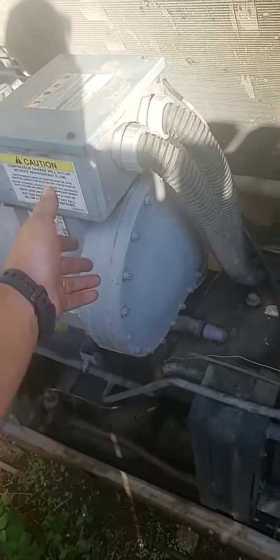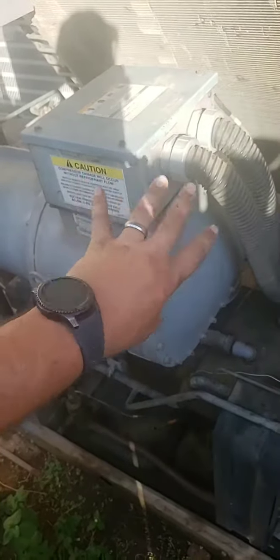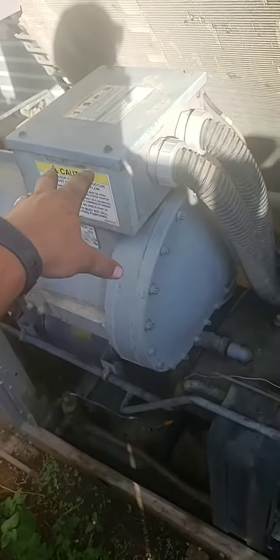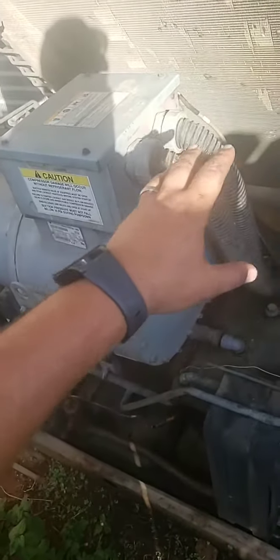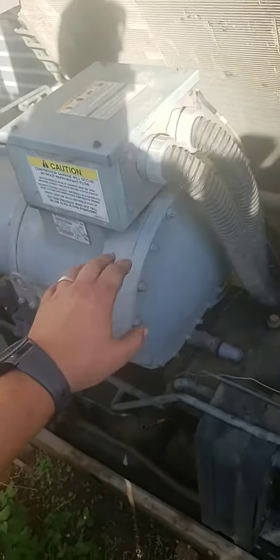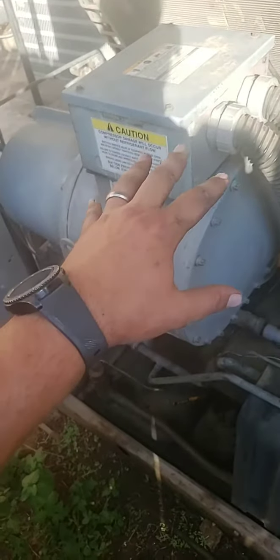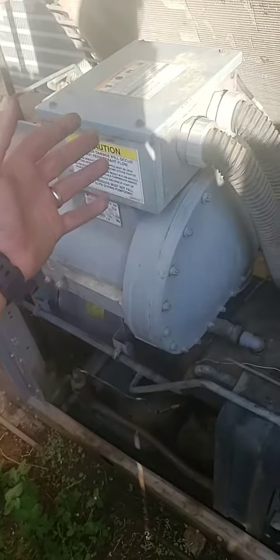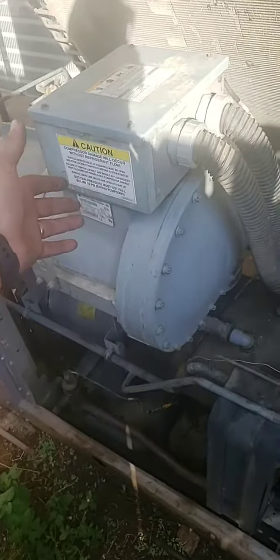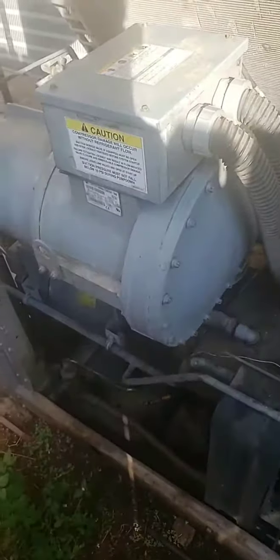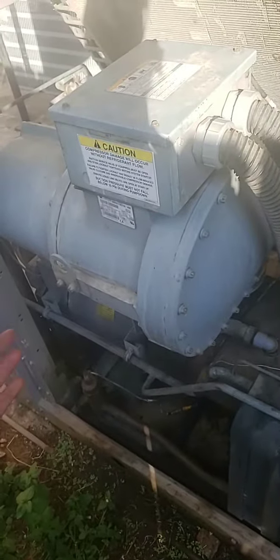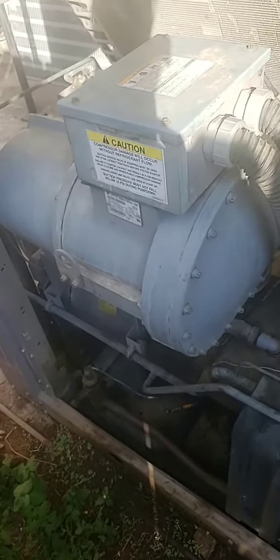Another issue is if this compressor ever starts up and it's tripping out the overloads as soon as it starts, and say you do a teardown on it and you meg it and everything checks out electrically, it could be that slide got stuck into a fully loaded position. And so these compressors, they will not start up if they're fully loaded. So for example, don't quote me on it, but if this is a 70-ton compressor fully unloaded, it may be doing 40 or 50 tons worth of actual BTUs it's processing at minimum load.